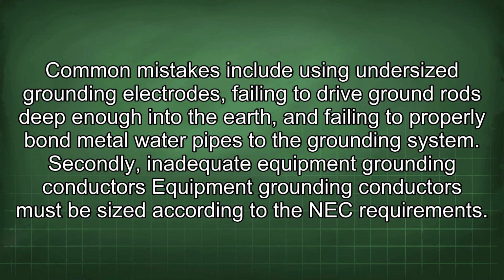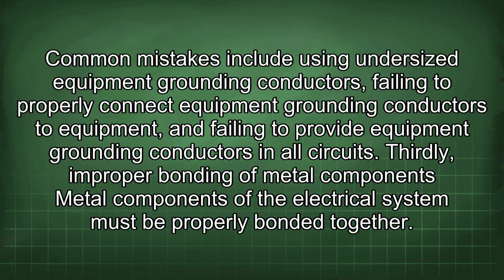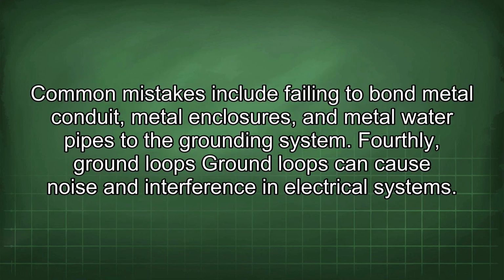Secondly, inadequate equipment grounding conductors. Grounding conductors must be sized according to the NEC requirements. Common mistakes include using undersized equipment grounding conductors, failing to properly connect equipment grounding conductors to equipment, and failing to provide equipment grounding conductors in all circuits. Thirdly, improper bonding of metal components. Metal components of the electrical system must be properly bonded together. Common mistakes include failing to bond metal conduit, metal enclosures, and metal water pipes to the grounding system.